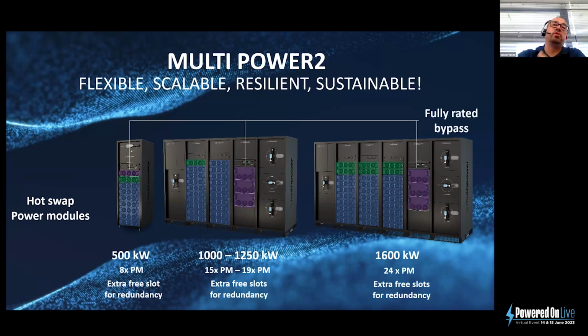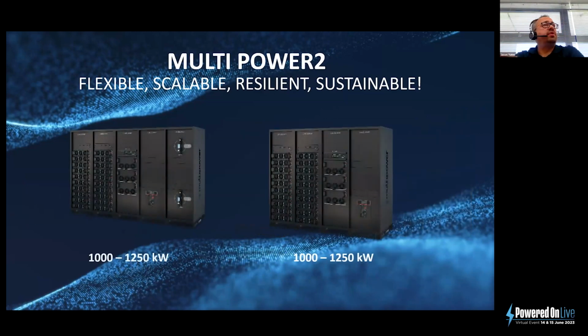So again, if the event has a problem, it has a fully rated bypass system. And also, within these cabinets you have full flexibility. You can see down the left is a 1, a 1.1 and a 1.25 megawatt solution with switches. Some people want the input and output switches to suit the installation. And on the right there, you will see the same installation where you have the system without any input switches.